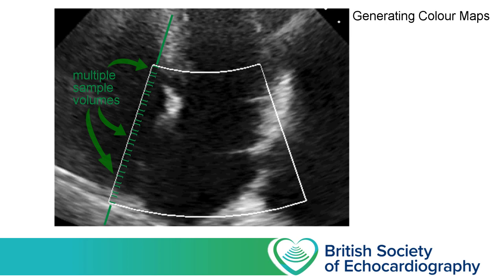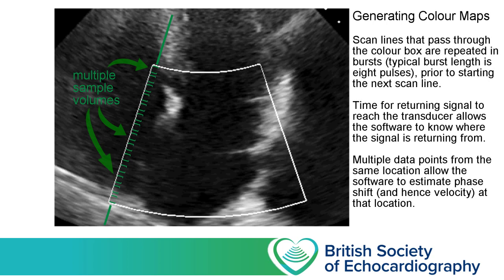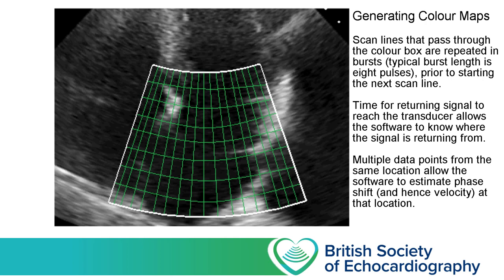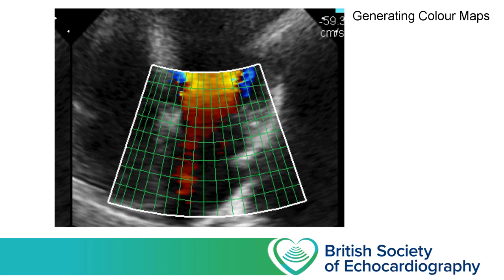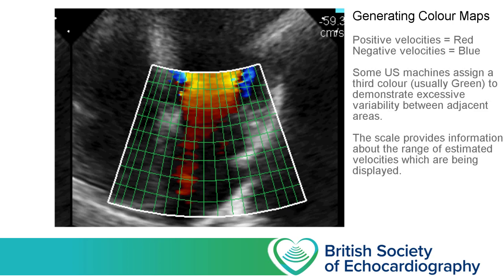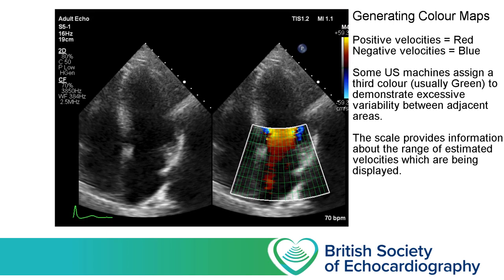The machine can't estimate phase shift from a single piece of information — it requires multiple values from the same location. So those scan lines that pass through the box are rapidly repeated, typically around 8 times, before moving on to the next scan line. Once there's been enough time for the scan line to sweep through the colour box, we end up with a grid of estimated velocities which can then be represented as a colour. By convention, positive velocities moving towards the transducer are represented with a shade of red, whereas negative velocities away from the transducer are represented with shades of blue, with brighter shades representing faster velocities.